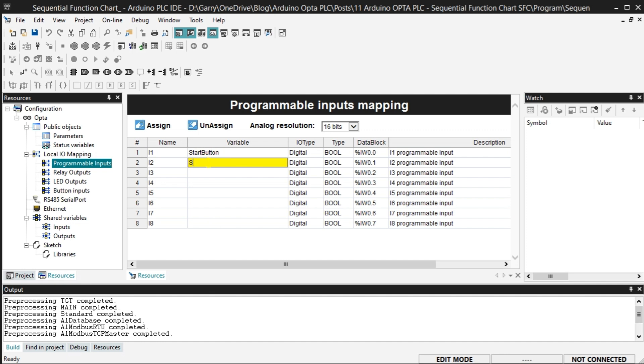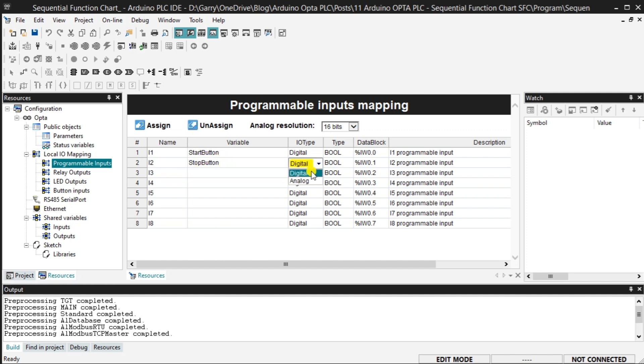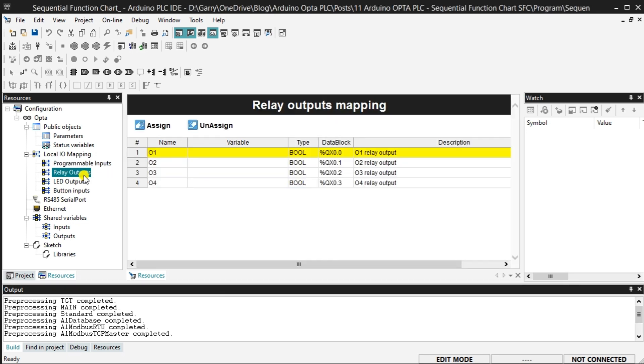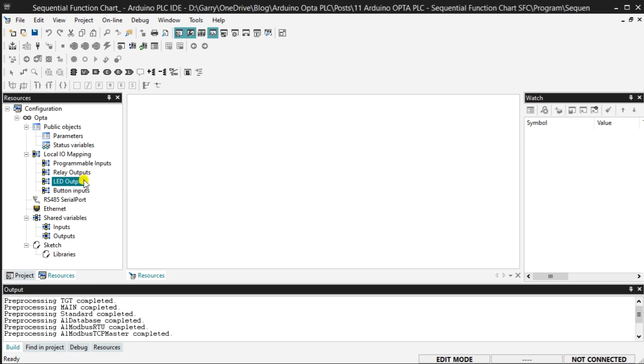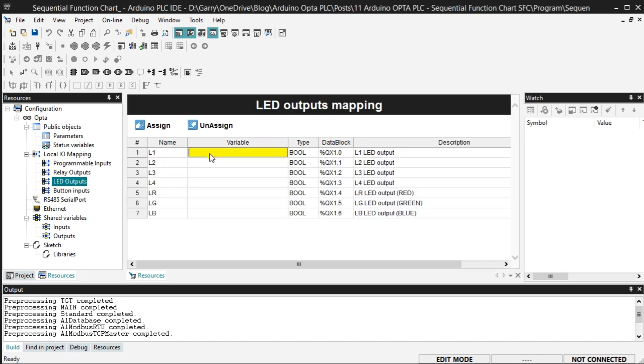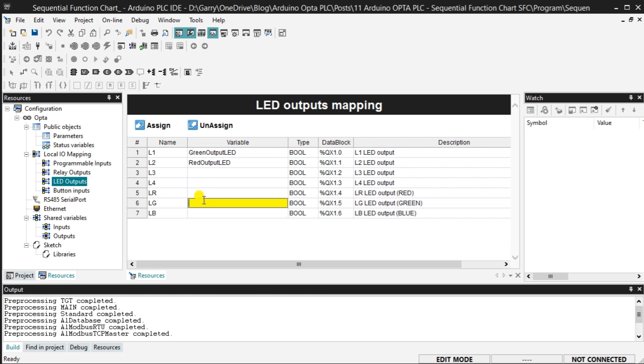Under I/O Type, we can select Digital, Default, or Analog. The Analog resolution can also be selected for the inputs. Select Relay Outputs that display the Relay outputs mapping. We can once again assign a variable to the relays that we will use in our Sequential Function Chart SFC program. Select LED outputs, which display the LED outputs mapping. These are the status lights on the Opta CPU unit. We will make these represent the relays in our program. Assign a variable name to the LED output that we will use. The Opta PLC also has a front LED that can be different colors. We will assign the green output to indicate that the Opta PLC code is scanning.